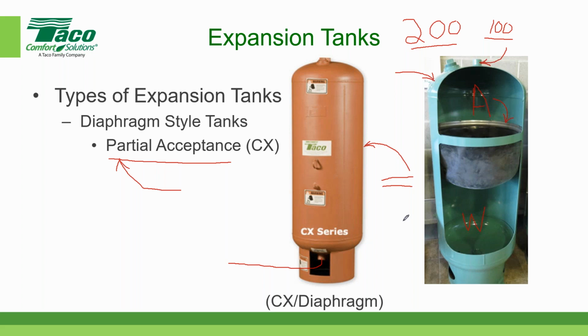If you have the new one, it could probably take less than half a day to change out the tank. That's called a diaphragm style tank. It's a partial acceptance tank—there are no full acceptance diaphragm style tanks. They're relatively inexpensive, but they cannot be repaired. If the diaphragm should fail for some reason, it has to be disposed of and you have to buy a new one. So those are the major categories of expansion tanks, and in the TACO world, that's called a CX style tank.